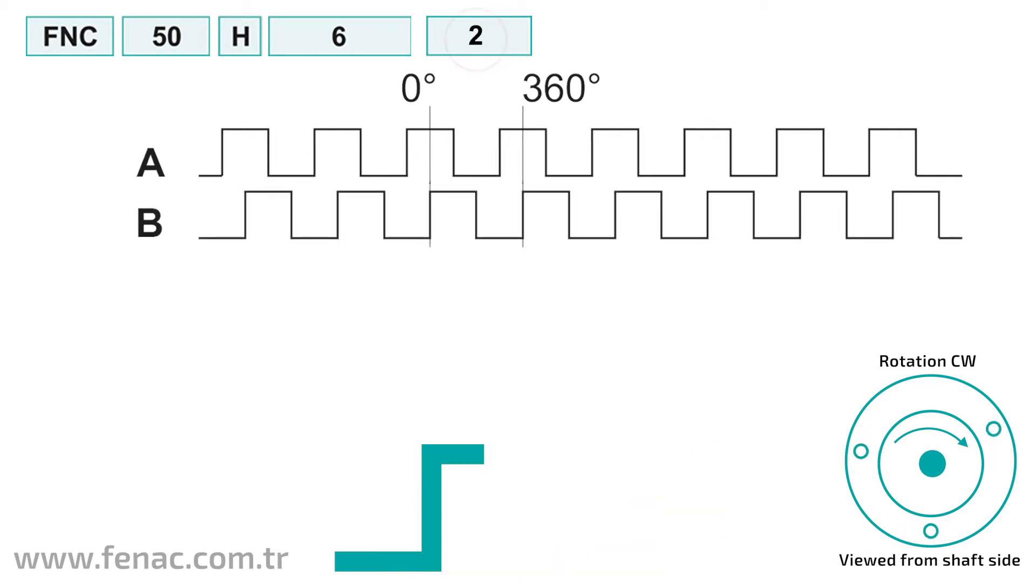If you want to determine the direction, A and B signals are used together. There is a 90-degree phase difference between the A and B signals. Direction can be determined from this phase difference. Also known as the quadrature encoder interface, the quadrature exchange between two signals helps you increase the resolution by four times.